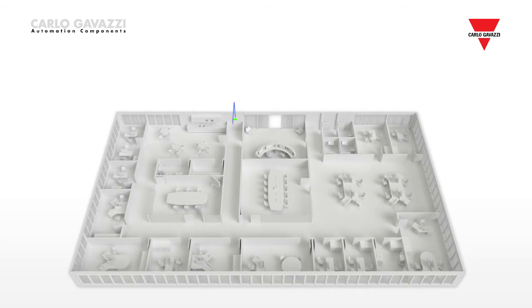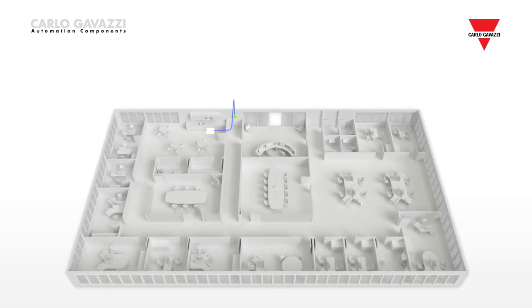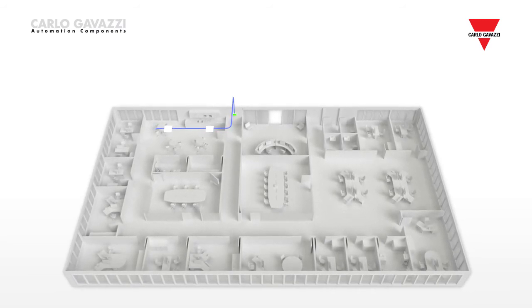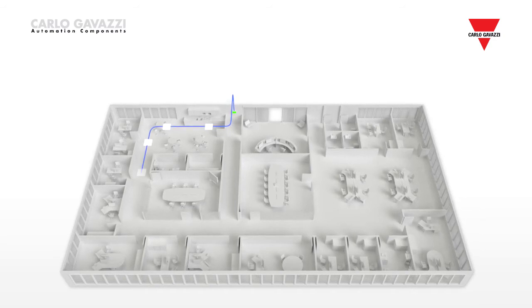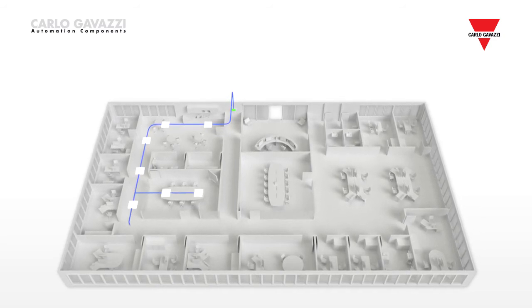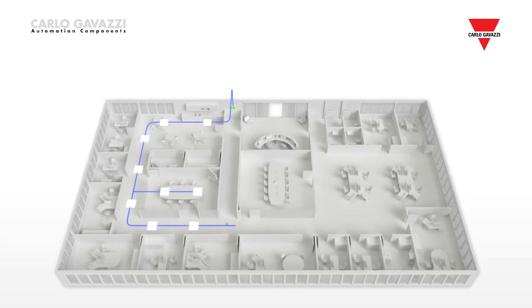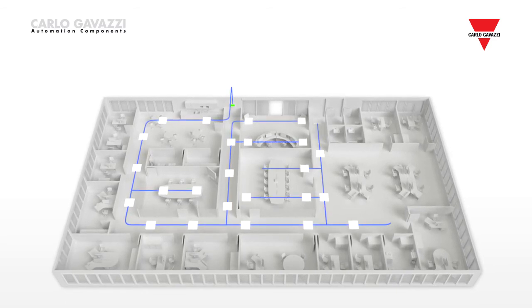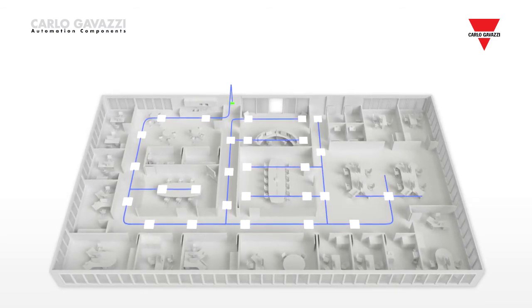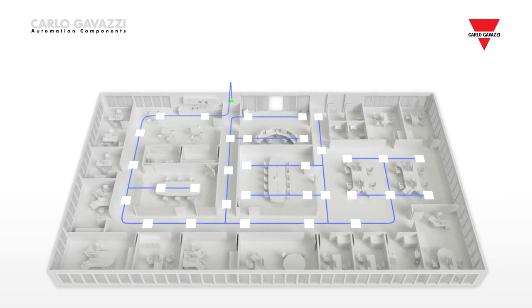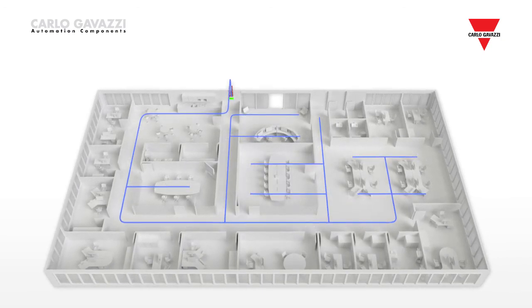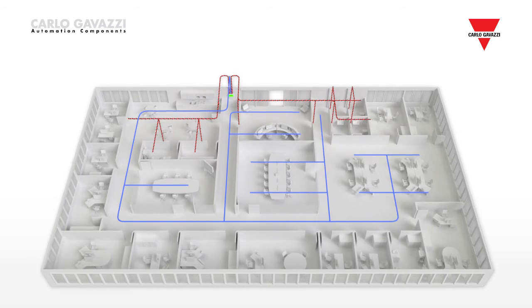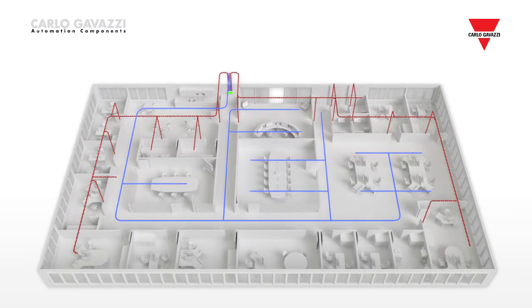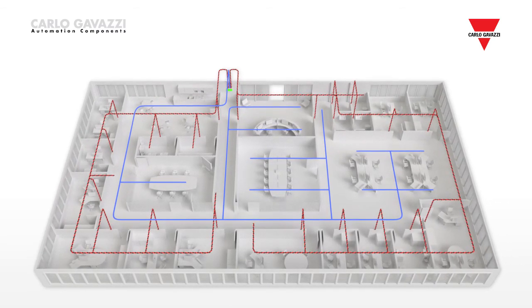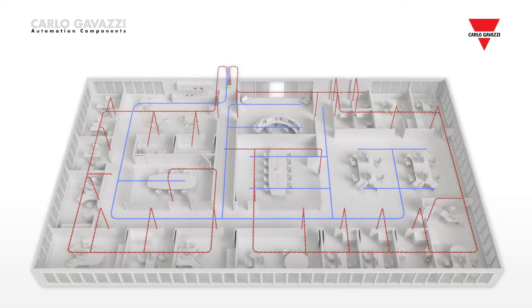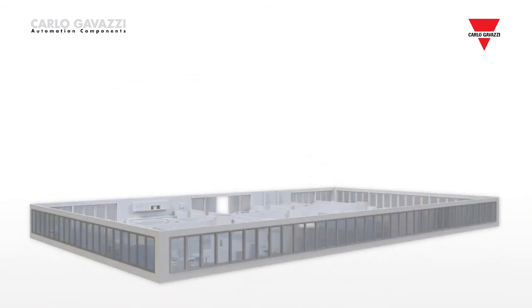Due to the long-distance capabilities and easy wiring of Dupline, the system is very suitable for linking multiple decentrally installed DALI controllers together. Signals from light switches, presence and movement detectors and lux sensors are managed directly on the Dupline bus using bus-powered components. The lighting control functions and the associated operating parameters can be monitored, controlled and altered from the BMS via BACnet. The lighting control system, easy to install and program, is completely scalable to any size of building.